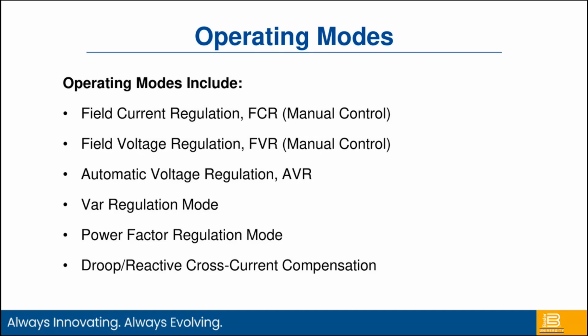So again, like those block diagrams, the basics there. But again, since we're looking at current, now we can look at that reactive component. That gives us the ability to do VAR control or VAR regulation mode. So now if I am tied to a utility or a much bigger source, such as a utility or a much larger generator, I may want to run that machine at a particular VAR output. So I want to control the amount of reactive load that I'm outputting.